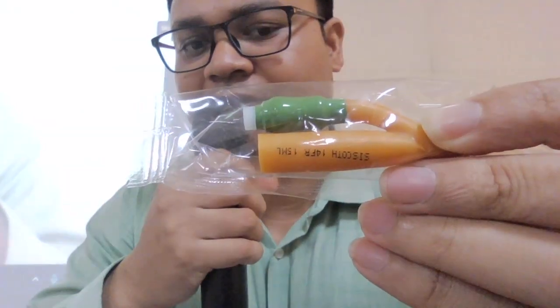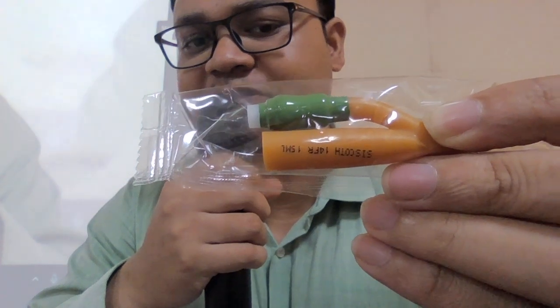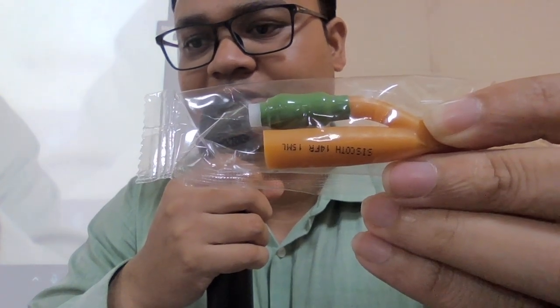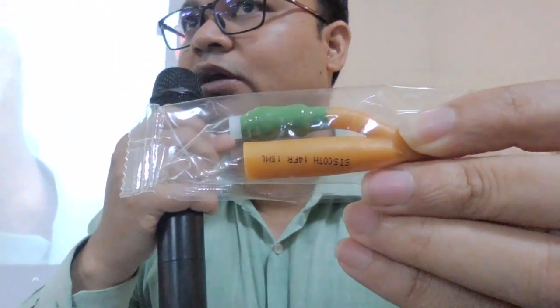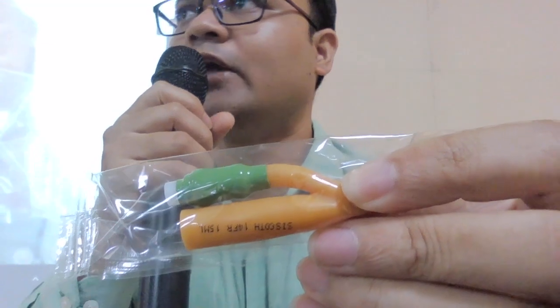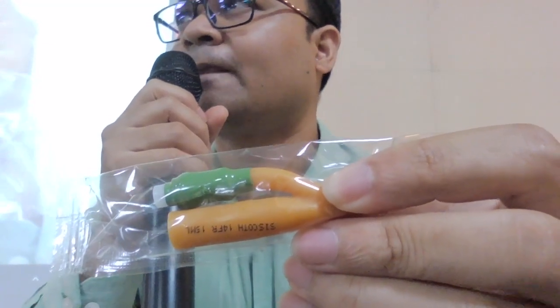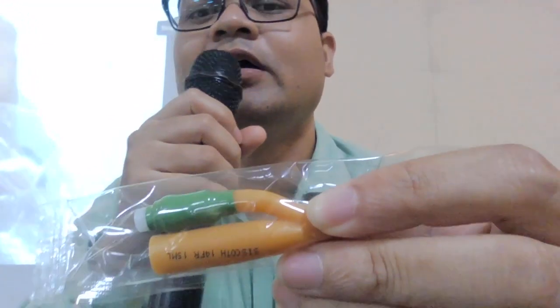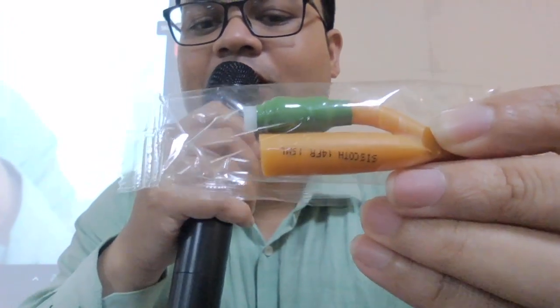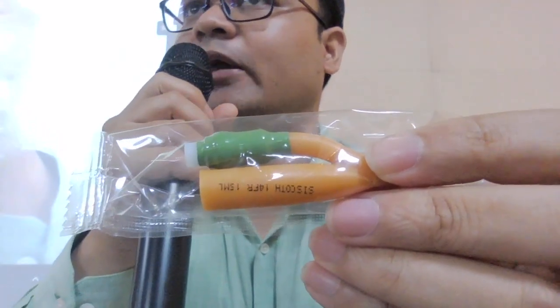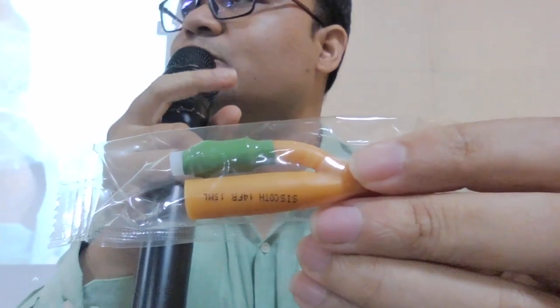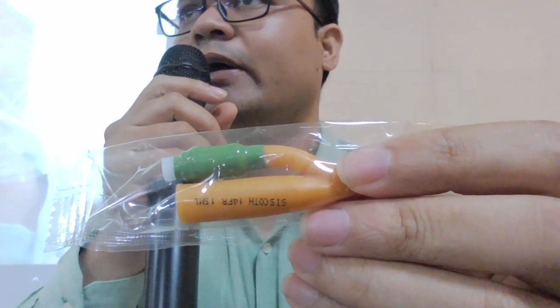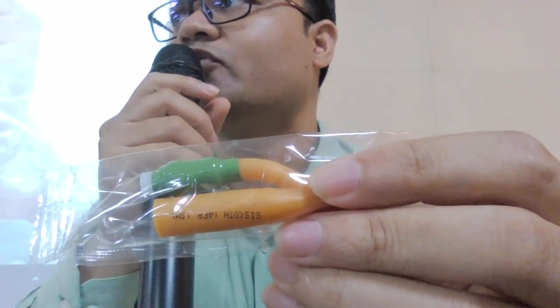And you see something written as 14, the one which is there in the center, 14 FR. That is 14 French. That is the size of the catheter. Okay. So how is this French related to the diameter of the catheter? Yes. Whatever the size is in French divided by 3, that is the diameter. This French actually corresponds to the circumference, and when you divide it by pi, that is roughly 3.14, so we take it as 3, that is the diameter of the catheter.